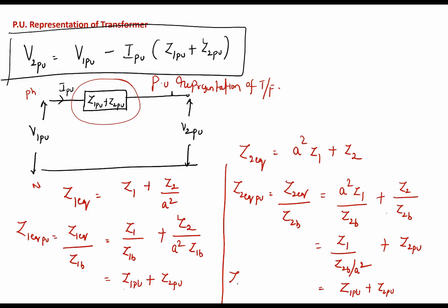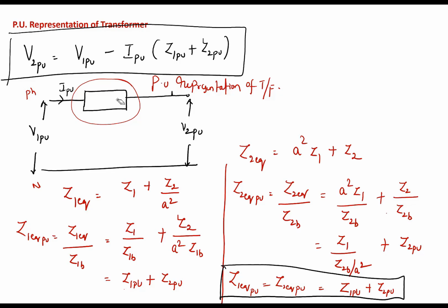So both Z1 equivalent per unit and Z2 equivalent per unit are equal to Z1 per unit plus Z2 per unit. So this value is nothing but the equivalent impedance per unit value. Whether you calculate Z1 equivalent per unit or Z2 equivalent per unit, both values are same. So here, instead of writing both, you can simply write Z equivalent per unit. Understand? So that's why in a transformer only the equivalent impedance referred to either HV side or LV side is given, because that is good enough to calculate the per unit value of the transformer. Okay, next.